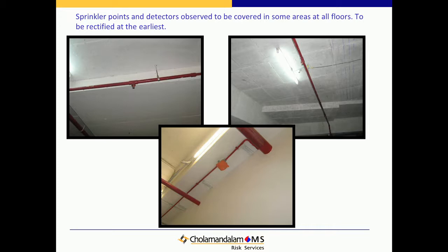See, this is what I told you. You can see the smoke detectors, that cover is still put there. The sprinkler system doesn't have that bulb. They just put that and then kept it. It will not sense. How does the sprinkler basically work? There will be a sensor. They'll have this one quartz bulb.